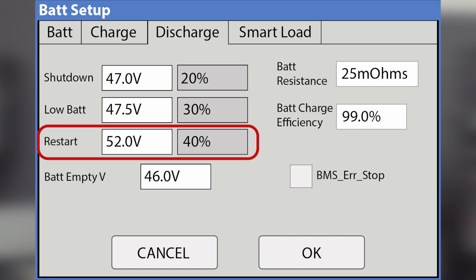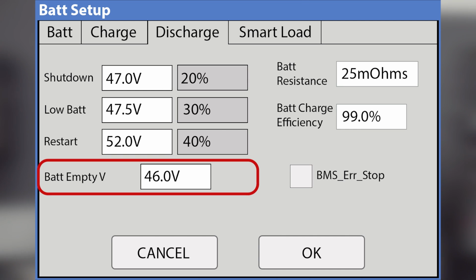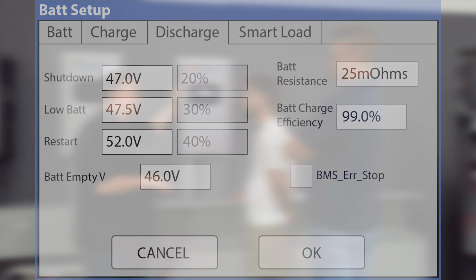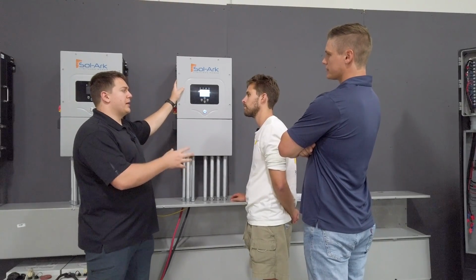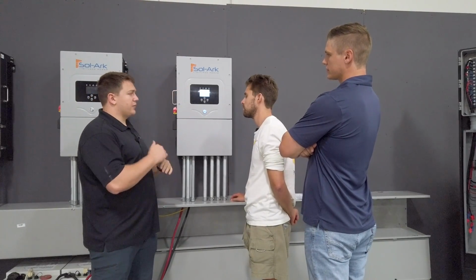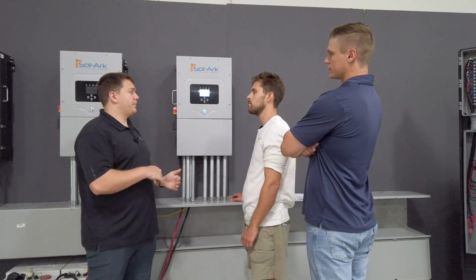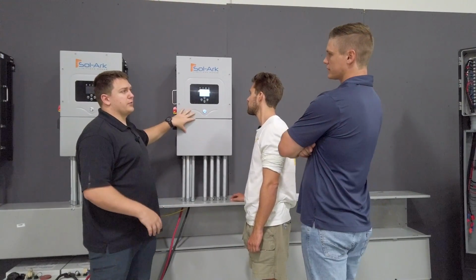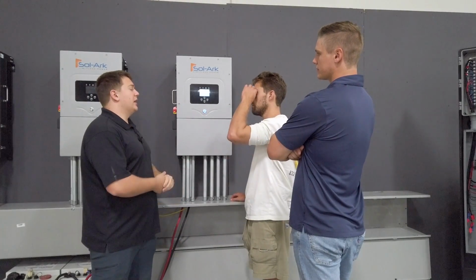And we do that so that there's a big enough gap between when it turns back on to power up your loads and when it shuts off. Because if those two numbers are too close to each other, you can imagine it would just oscillate. And then lastly, we have the battery empty voltage. This is a very important setting that you're also going to get from your manufacturer. This is a hard line in the sand: if we hit this voltage, we're going to turn off the inverter. We do this to protect the battery, because we want the inverter to turn off before the battery's BMS turns off. A lot of the BMSs have a hard line voltage sensor for whenever they shut down. So you don't want the battery to turn off while we're trying to power a load. You want it to be the other way around. It's more graceful. And so that's why we have this setting.